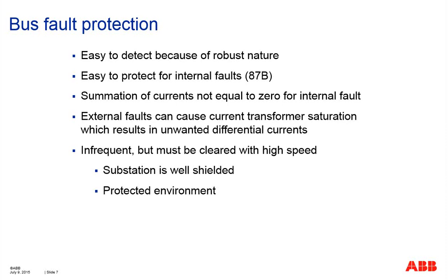So in other words, for an external fault on the busbar protection zone, the outgoing CT is very likely to saturate because it is sensing a significant amount of current going through it. That's why busbar protection must be very selective. It cannot operate under unwanted external fault situations. Okay.